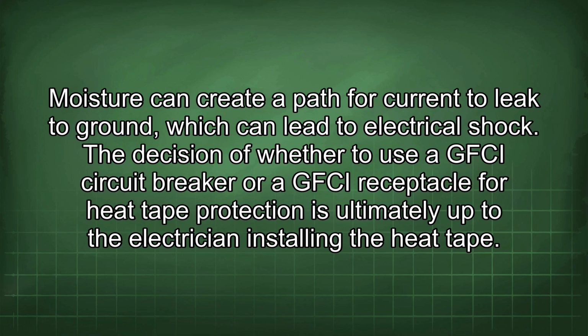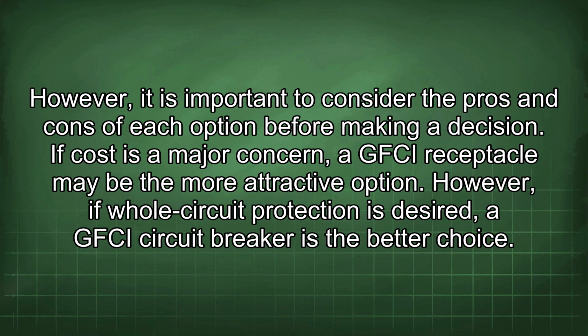The decision of whether to use a GFCI circuit breaker or a GFCI receptacle for heat tape protection is ultimately up to the electrician installing the heat tape. However, it is important to consider the pros and cons of each option before making a decision. If cost is a major concern, a GFCI receptacle may be the more attractive option. However, if whole circuit protection is desired, a GFCI circuit breaker is the better choice.